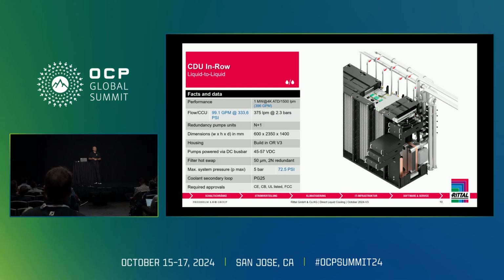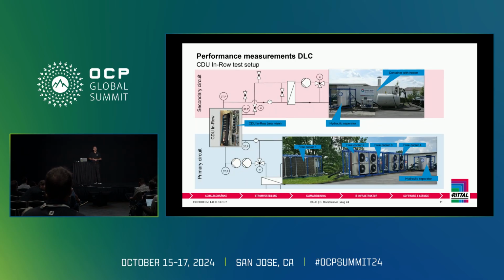So how do we know it's 1 megawatt? I mean, we could claim it easily and have no evidence of it. We set it up and we test it, of course. So within our facilities, or outside our facilities in this case, we basically pulled in a 2 megawatt heater unit, fuelled on the secondary circuit, hooked it up to the primary circuit, and we tested it. And we ramped it up to full power, just over 1 megawatt. We watched it stabilize, and we nominalized, and we recorded all of the output from it. And some of the cooling curves we got from it, it did exactly as we predicted. So we're confident, or more than confident, we've proven it's 1 megawatt with a 4K approach temperature delta.